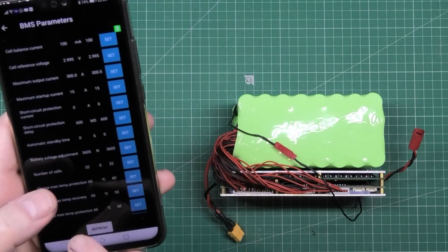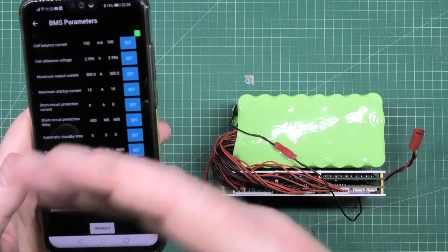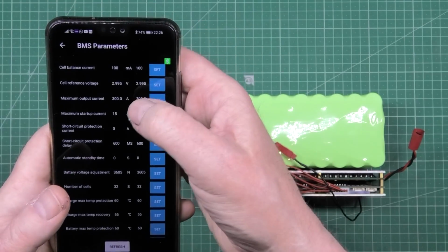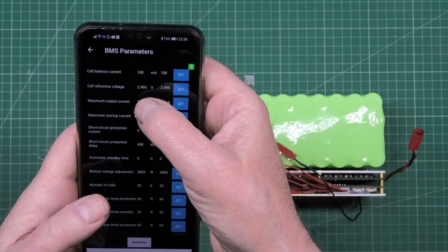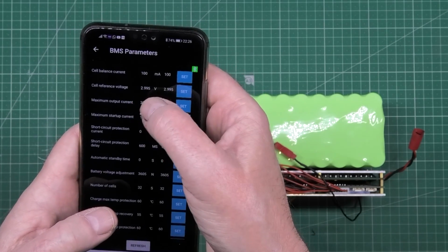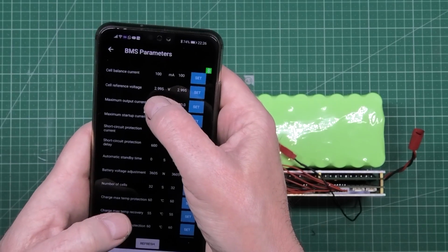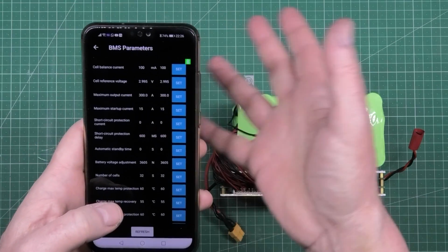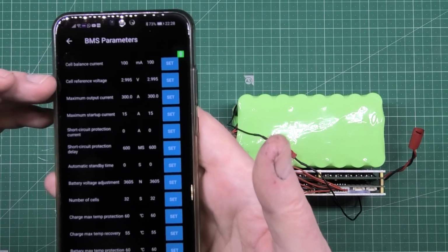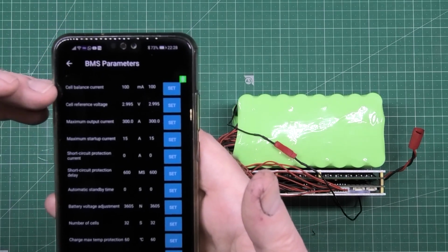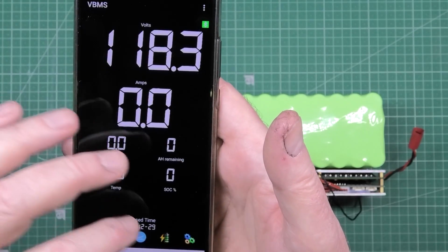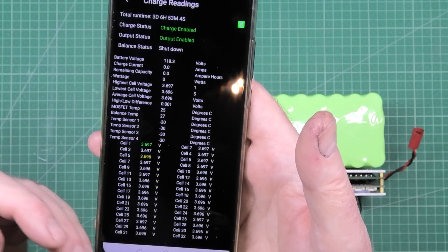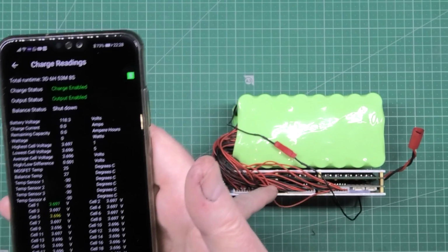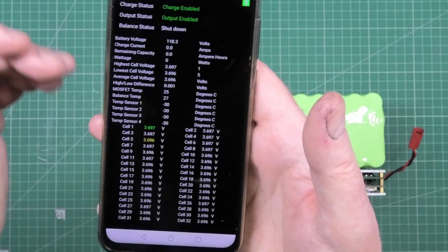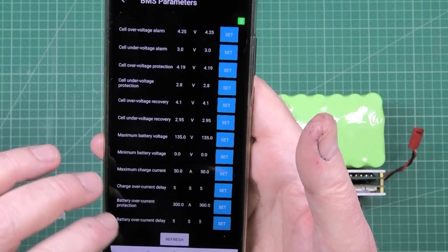Now I think by default that's set at 3 volts. We'll say this is reading 1 millivolt high. What I'll do is change that to 2.999 as opposed to 3.0. You do not type the battery voltage you've measured into that, because it's wrong. Always go in small increments, don't go in large increments until you know exactly how much you can drop or raise it. Keep going back into this screen - when you make an adjustment, check if it's actually changed to what you've read, then keep increasing or decreasing accordingly. That's all I can explain on that one.